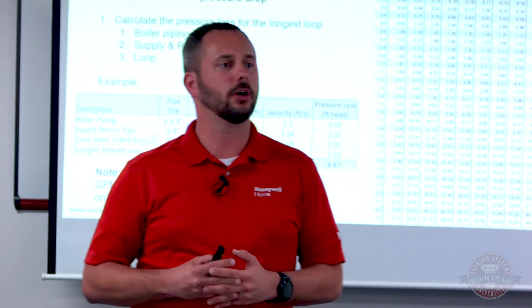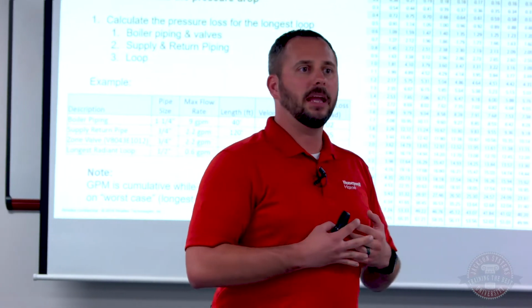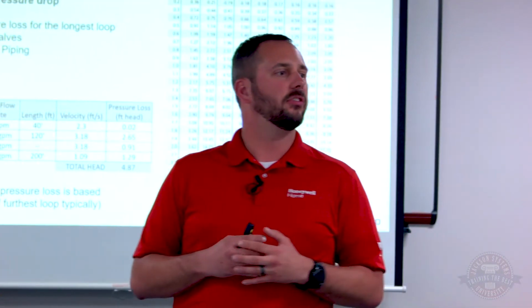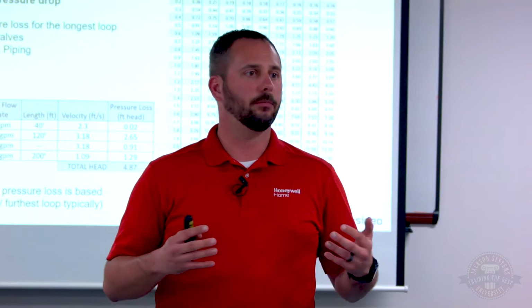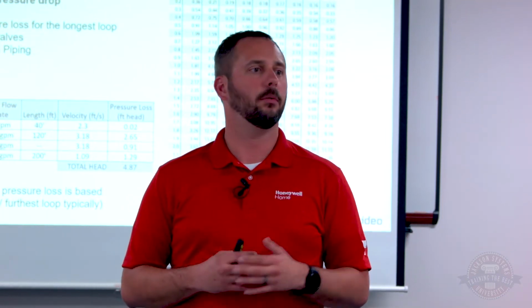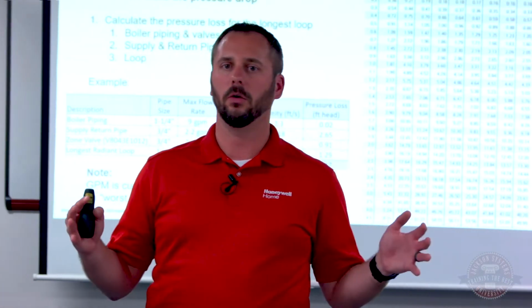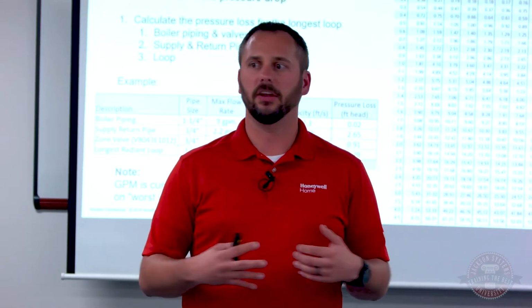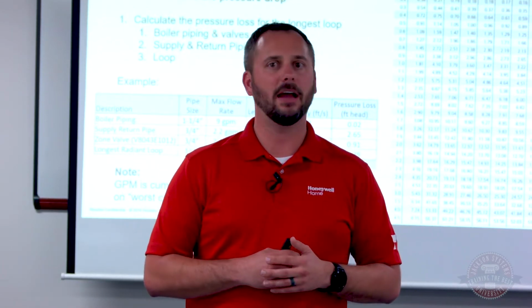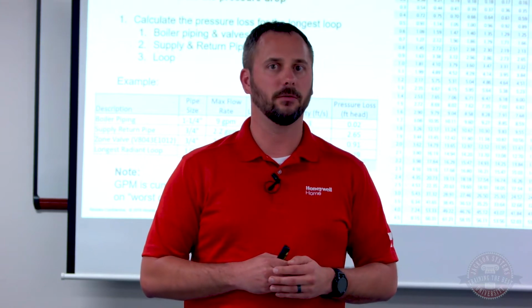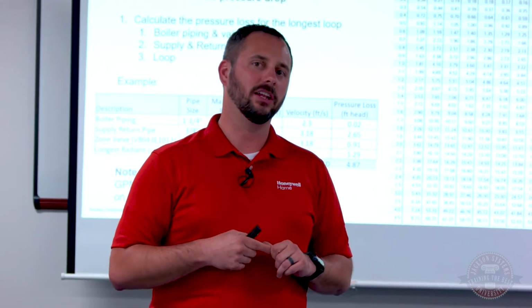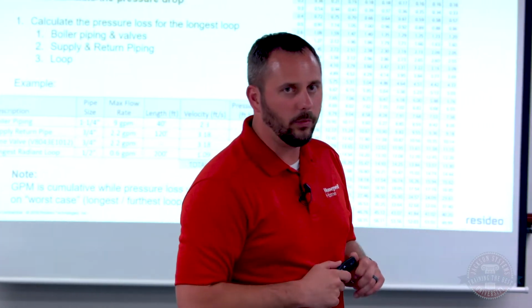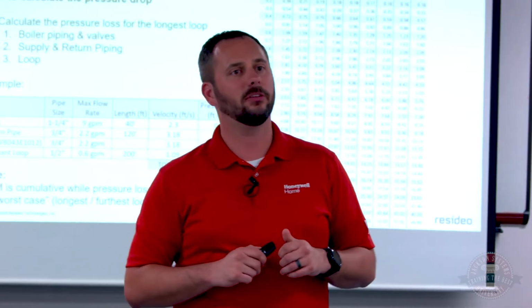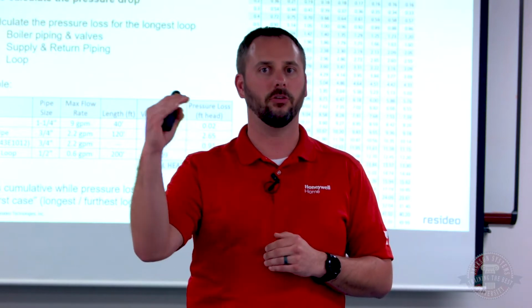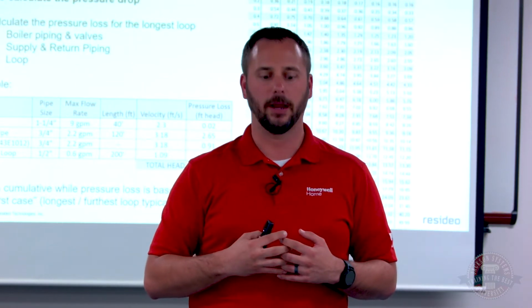So when we calculate the pressure drop, you need to calculate it based on the capabilities of the worst case scenario. So if we are looking at gallons per minute, let's say we're sizing a central pump. I'm going to use the example of one pump with multiple zone valves. That pump has to be capable of delivering the flow to every single zone in the system. So again, let's say it's a 100,000 BTU boiler. It's got to be capable of driving 10 gallons a minute on a 20-degree temperature differential. We need that pressure rating to really identify the pump. So what we need to do is figure out where the water is going. Water always takes the path of least resistance, but we need to figure out which is the worst resistance, and that's what that pump has to be capable of delivering.